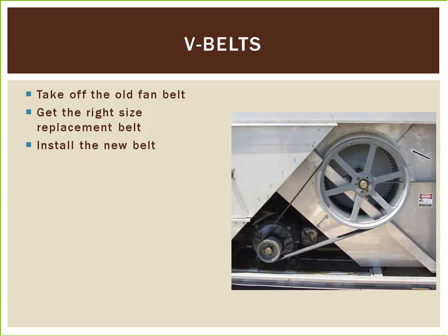A helpful fan belt repair tip is that the belt should be taut and should not squeal when the unit is running. To determine if it is tight enough, remove anything that could get caught in moving parts and turn on the unit. If the belt doesn't squeal, then it is probably tight enough. When you tighten the belt, be careful not to get it too tight. If it is too tight, it will put unreasonable stress on components and lead to failure over time.